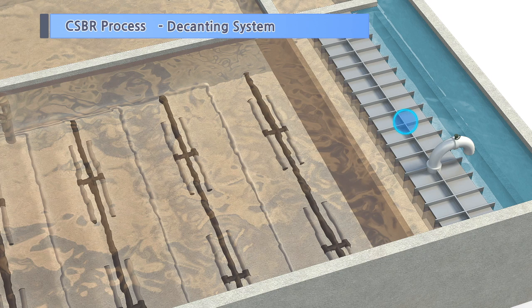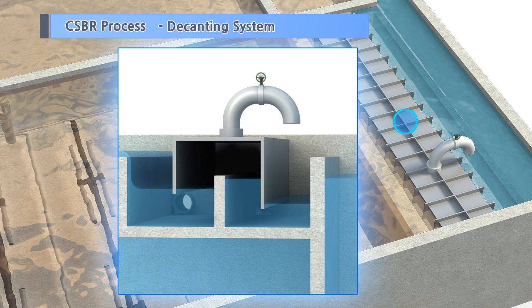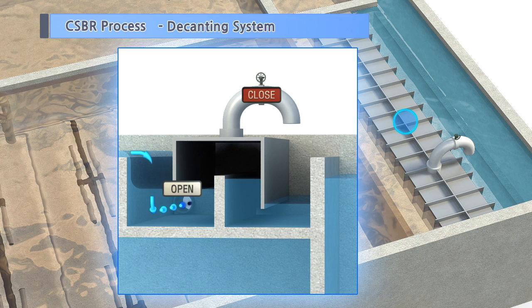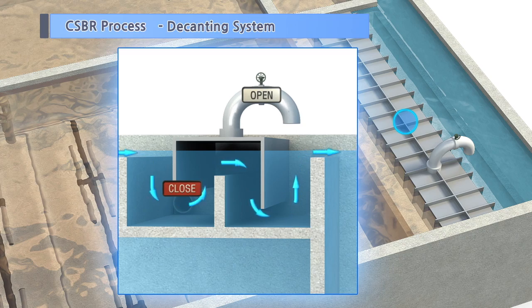The decanting system is a fixed discharge device which adjusts the discharge of the treated water by using air pressure. It consists of a hood and a valve to control the air discharge. During normal operation, the discharge of the treated water is blocked by the hydraulic structure of the decanter. When it is time to discharge the treated water, the air valve opens to discharge the air in the hood, which naturally discharges the treated water due to the water level difference.